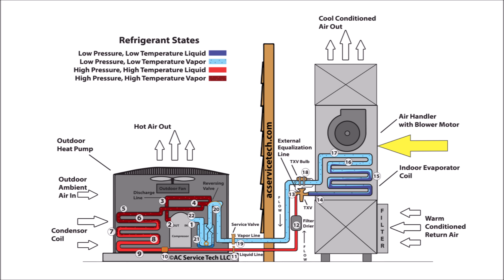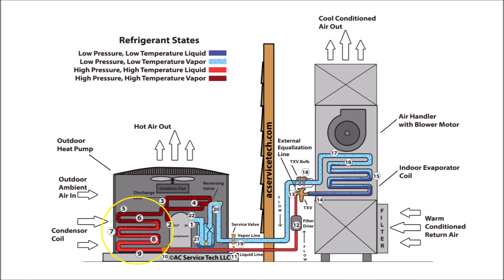On the right-hand side of the picture, you can see we have an air handler sucking air across the indoor coil. In cooling mode, that indoor coil is referred to as the evaporator coil. On the left-hand side of the exterior wall, you have an outdoor unit — this could be referred to as a heat pump — and the coil in this unit during cooling mode is considered the condenser coil. Up top you see the refrigerant state, with a color guide so you can follow along with what state the refrigerant is at during the refrigeration cycle. If you see two colors inside a tube, that means the refrigerant is in the saturated state at that part of the cycle.